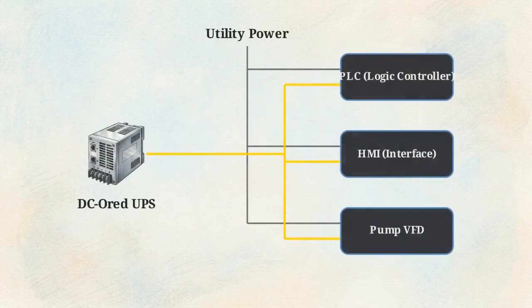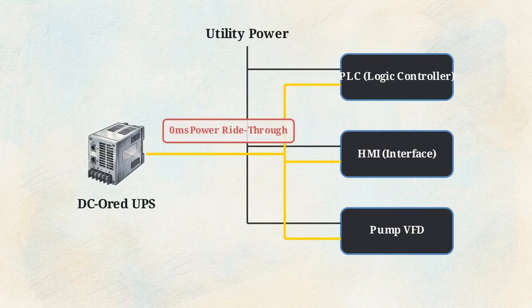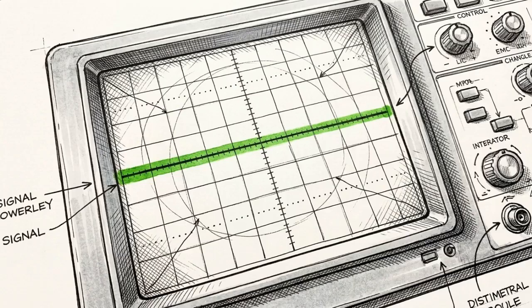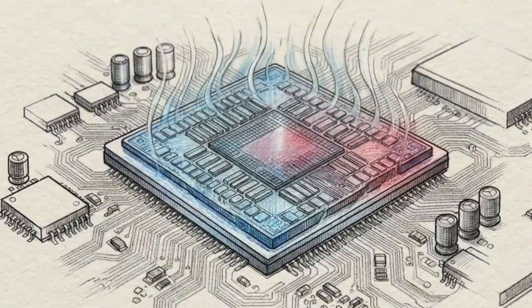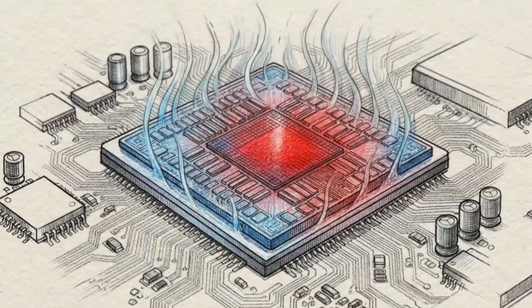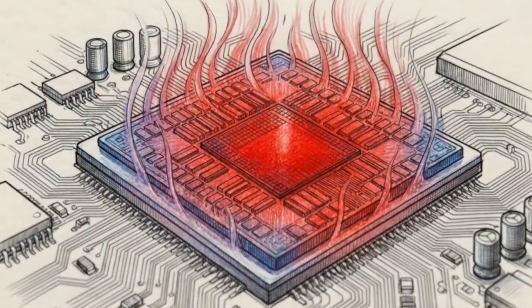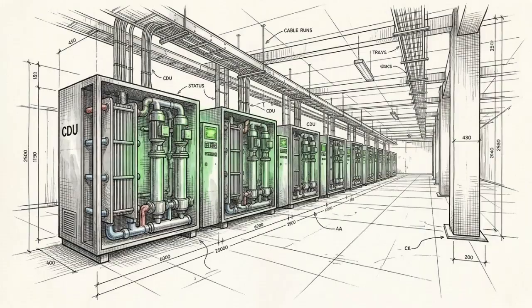The unit's programmable logic controllers, human-machine interface, and at least one primary pump drive are wired into a continuous DC-ORed UPS buffer, guaranteeing a sub-20 millisecond power ride-through during utility transfer gaps. High-density AI chips will hit their thermal limits and throttle within 5 to 10 seconds of flow loss. That sub-20 millisecond mechanical response is a mandatory requirement for achieving uptime Tier 4 continuous cooling compliance.